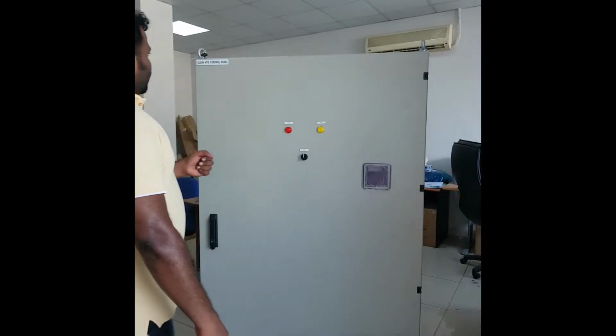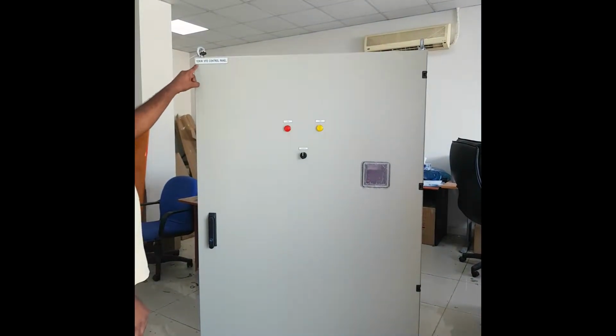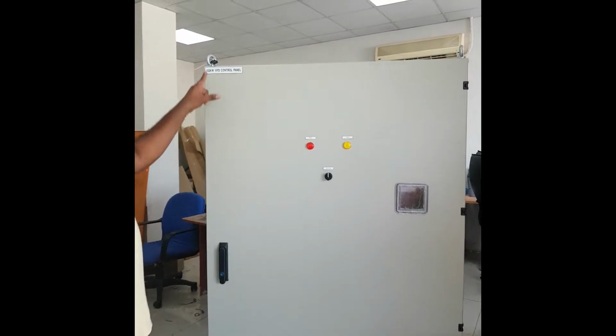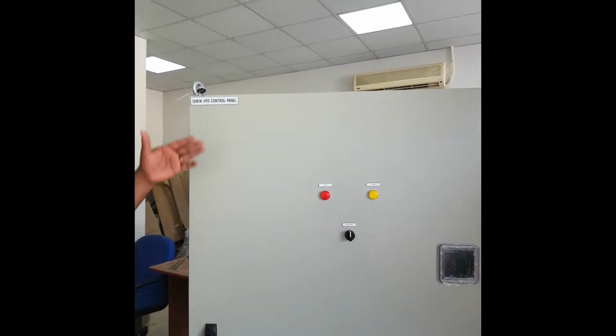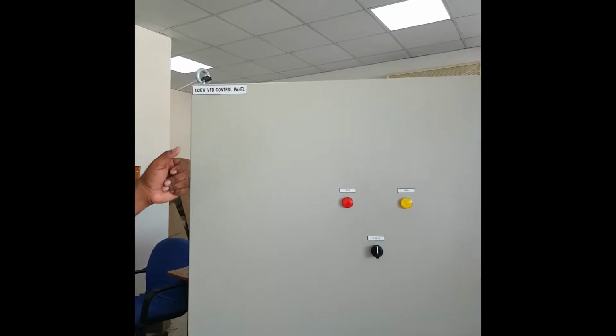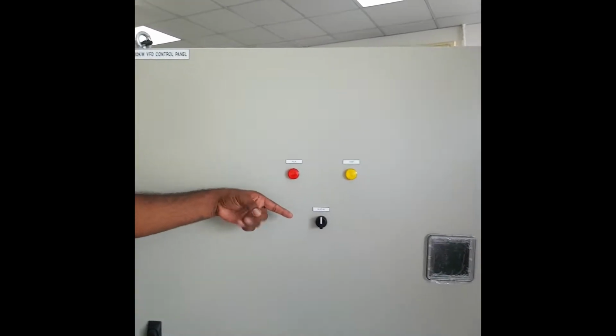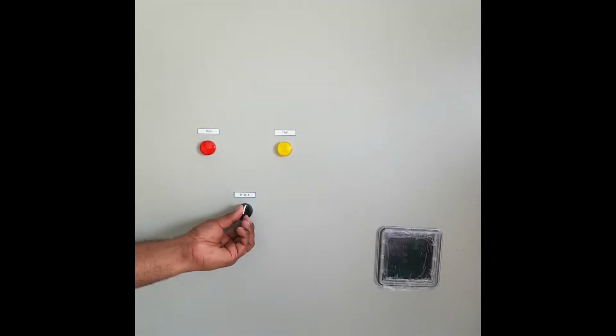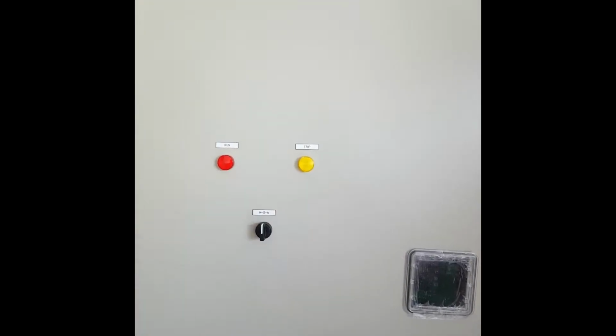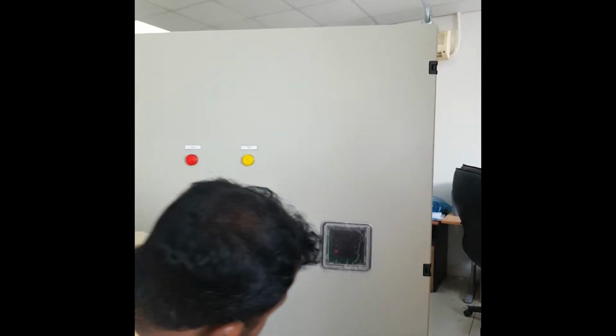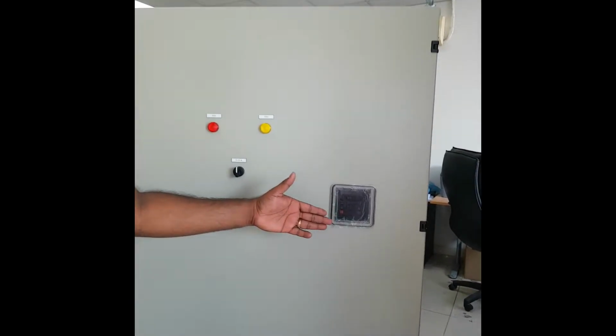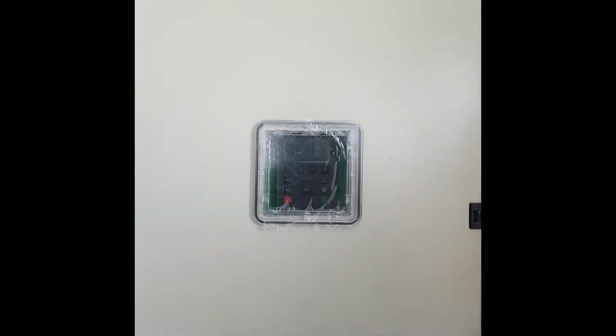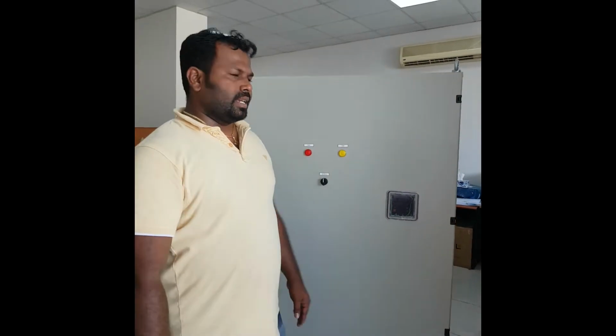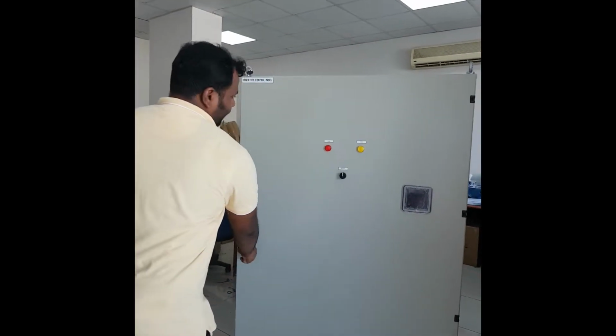So this is the panel. You can see a 132 kilowatt VFD control panel in a metal enclosure. On the panel you can see a HOA selector switch, run and trip indication lamps, and a viewing window. Through this window you can see the VFD display also. Now we will see inside how this panel is fabricated.